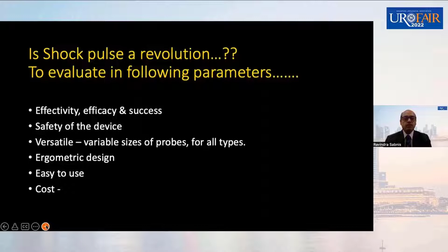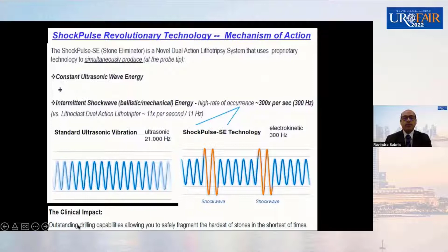Now, if you consider the efficacy, effectivity and success, Shock Pulse is a revolutionary technology. As you can see from this graph, this is how the ultrasonic energy is delivered at the tip of the probe. That is 21,000 hertz, so that is the frequency which is delivered. And this brown is the lithoclast, or the ballistic energy, which is delivered at 300 hertz. So the combination of these two is a very effective way of breaking the stone.